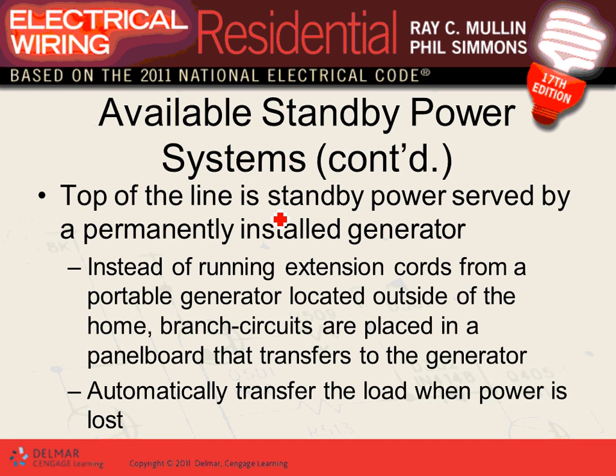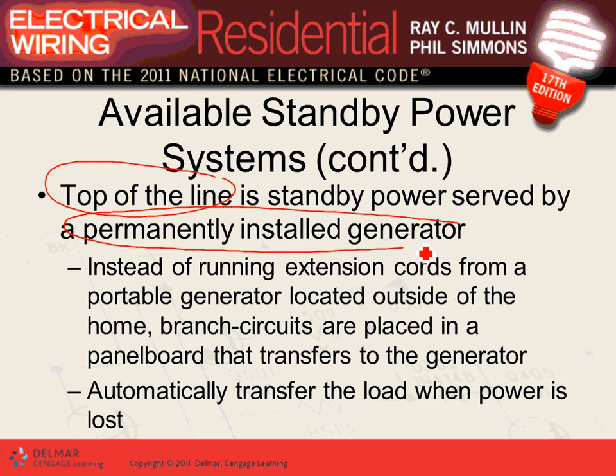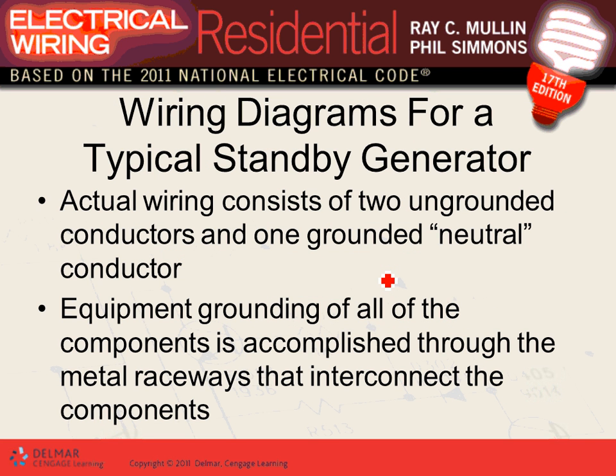Okay, now moving forward, the next step, guys, is to go to the so-called top of the line. Instead of portable, guys, now we have permanent. Now we have a permanent generator. Can you guys see the permanent generator? Instead of running an extension cord, now there is no extension cord whatsoever. Everything is permanently wired, you'll see. From the generator, you have a feeder going to the transfer switch, which automatically transfers the load when power is interrupted.